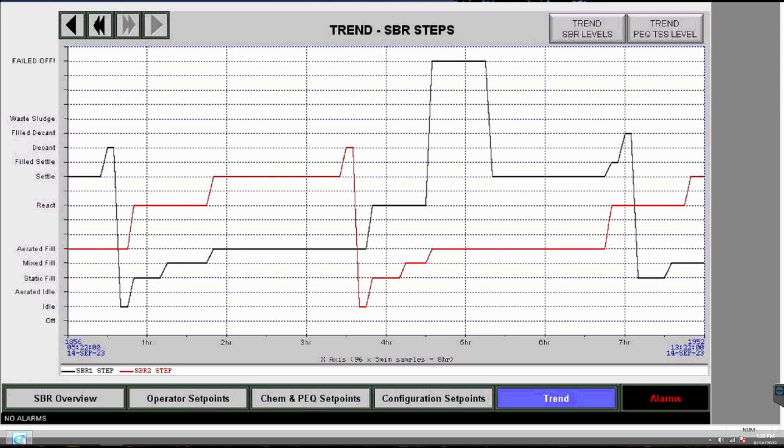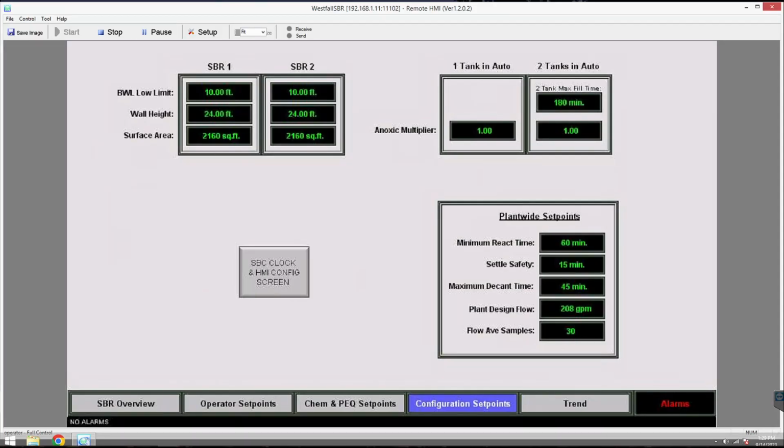Maybe I didn't look. So one of the things I would recommend that you look at is, I don't know if you have a trend chart you can look at, or an event log where you can look at your influent pumps to see how often they're cycling on and off. Yep, we do. But one of the things you could do is increase that samples set point to get two start and stop cycles in on your influent pumps. And what that may do is hopefully give you a better picture of what your influent EQ is.